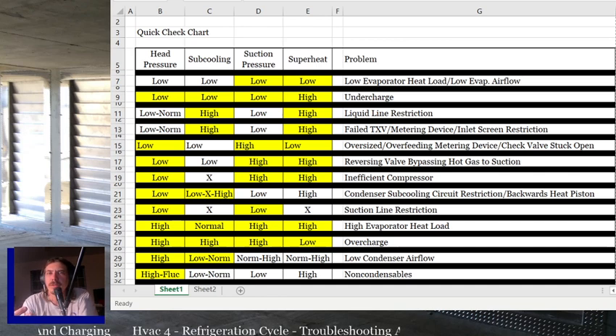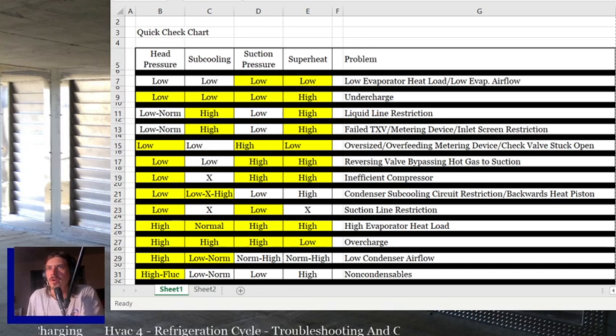Those are relatively rare. Rare enough that I don't think you need to be taking discharge pressure or looking at it in a chart all the time. You'll get used to this stuff anyway, but this is what you need for 95 to 99% of cases. So I kind of like it just laid out a little more simple. If you guys have never seen the one in the back of the catalog, it doesn't even give you this much. It just says head pressure, suction pressure, superheat, what you got, and whether those are low or high, and their charts are based off of that. But this will generally be good for you.